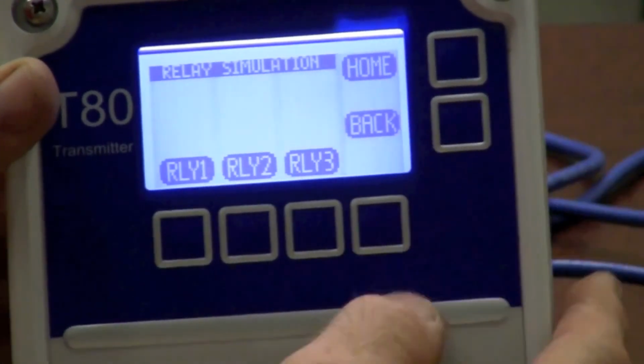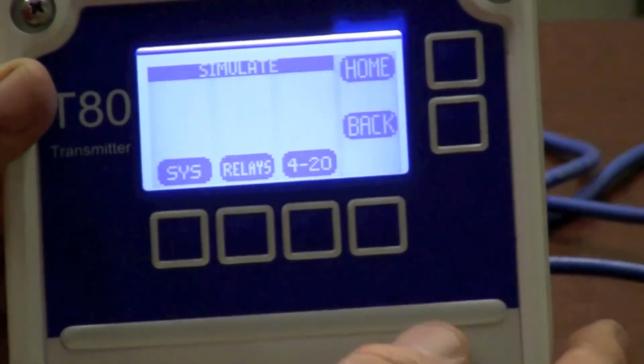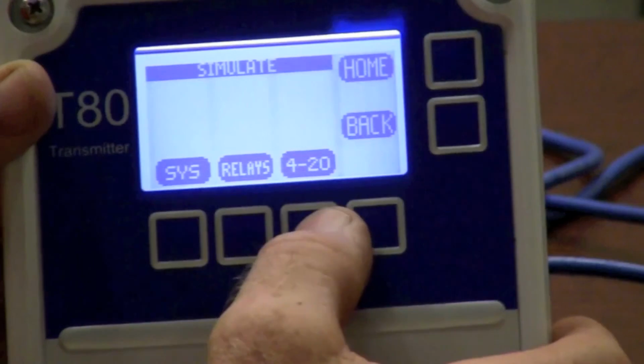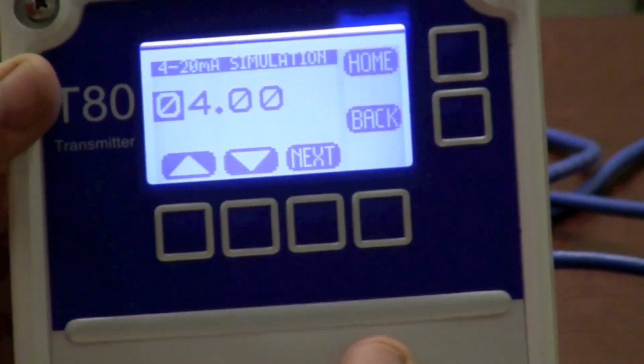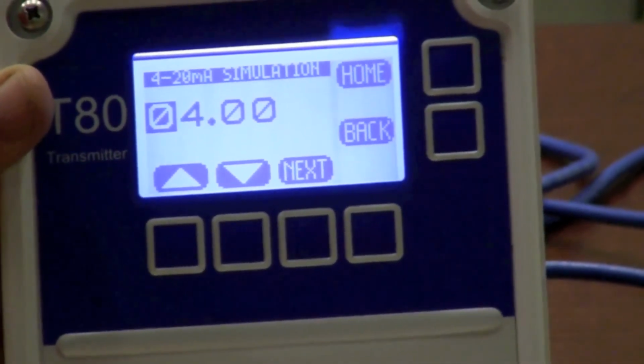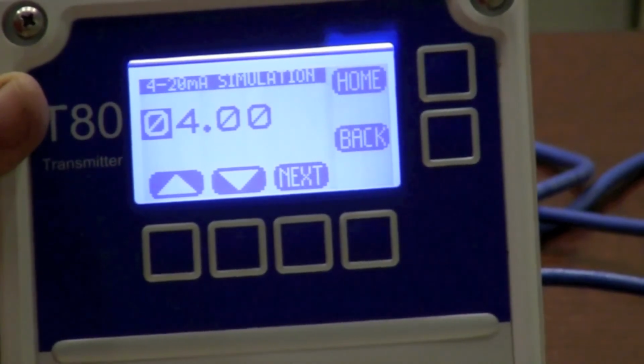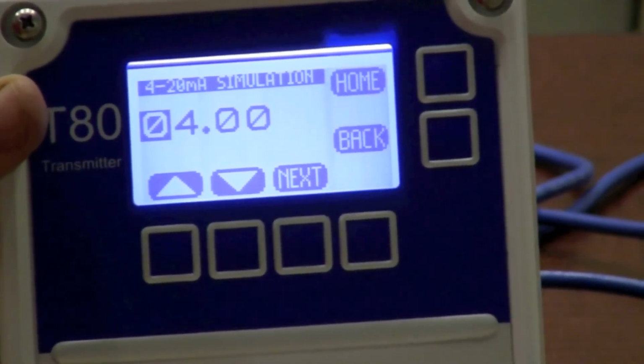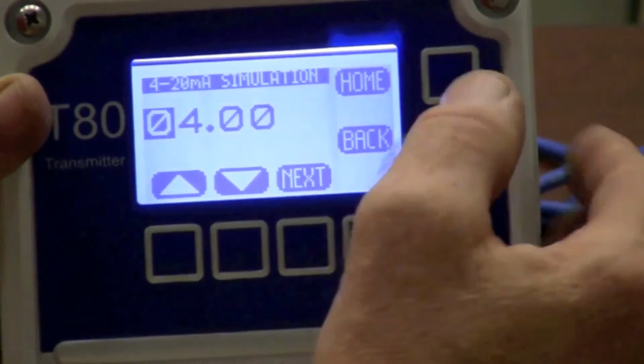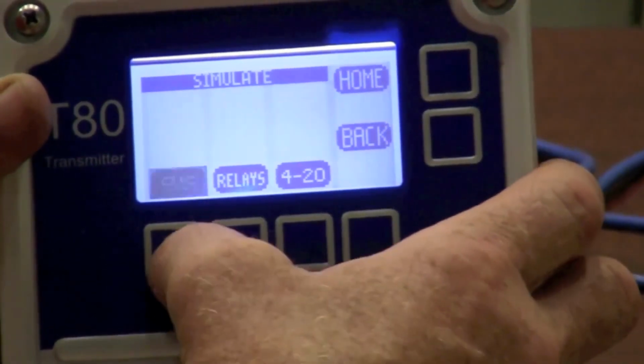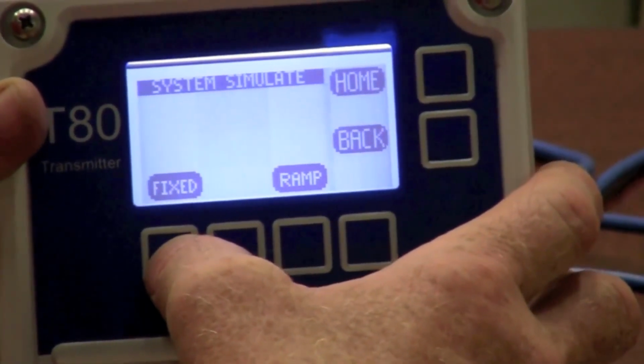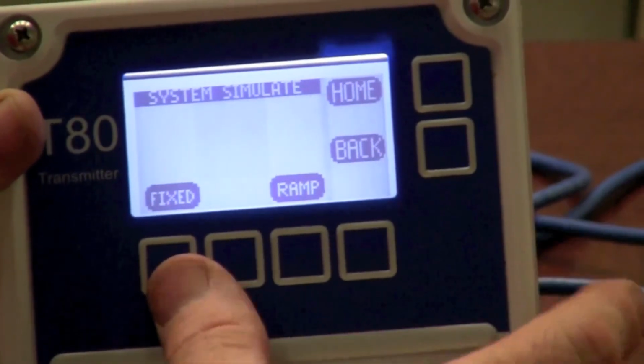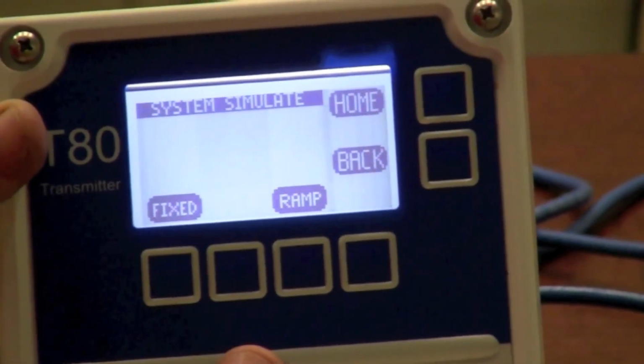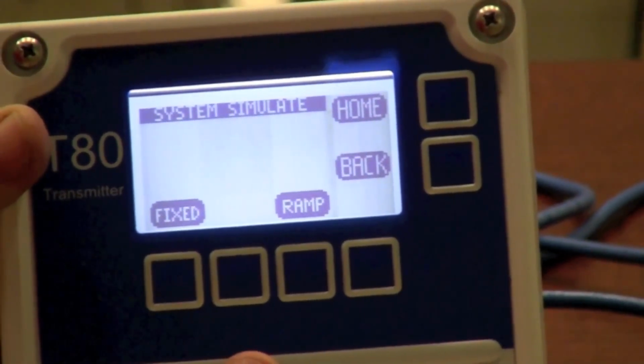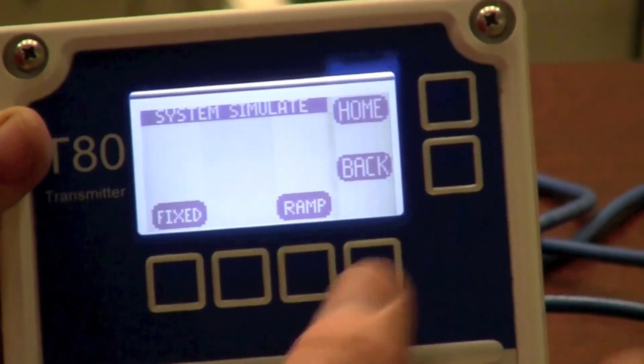Pushing the back key, I can come over and simulate my 4 to 20, ensuring that my PLC is scaled the same as my pH transmitter in the field, a very common error. Also, I have system simulate, and this allows me to ramp my analog output if I wish.